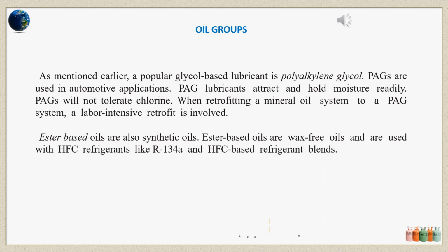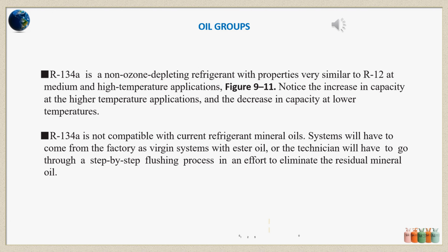Ester-based oils are also synthetic oils. Ester-based oils are wax-free oils and are used with HFC refrigerants like R134A and HFC-based refrigerant blends. R134A is a non-ozone depleting refrigerant with properties very similar to R12 at medium and high temperature applications. Figure 9-11. Notice the increase in capacity at the higher temperature applications and the decrease in capacity at lower temperatures.